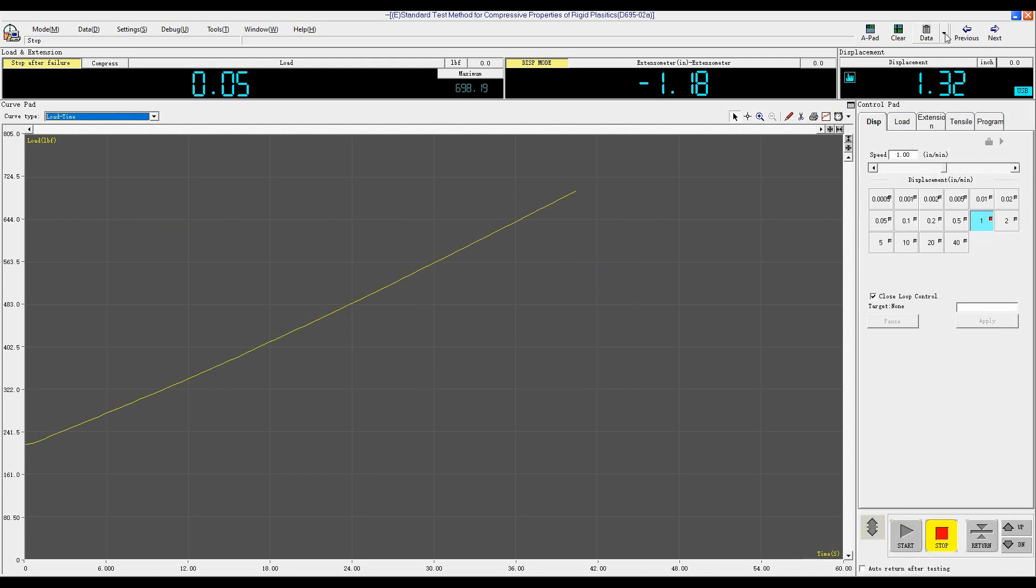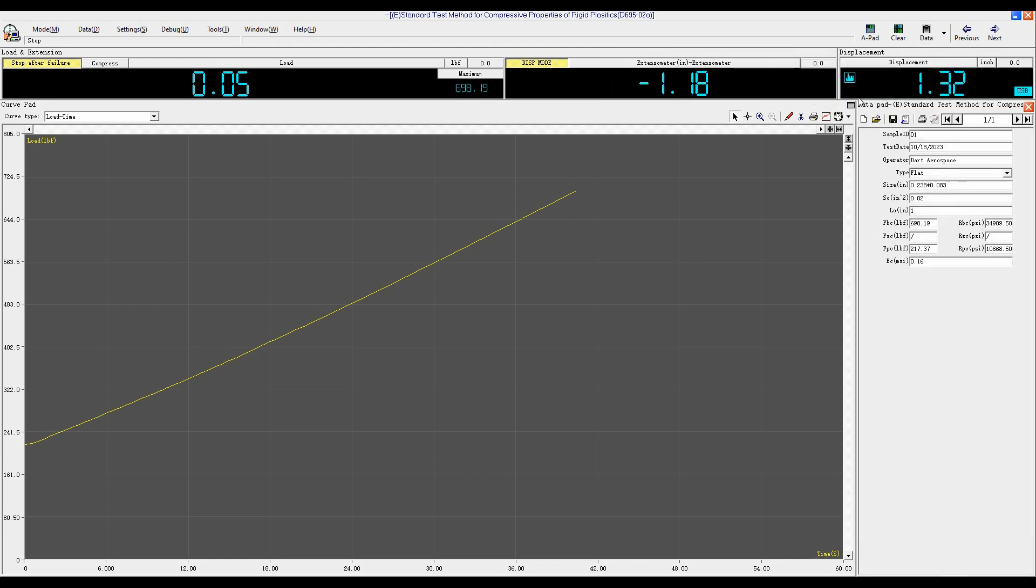Now we will perform a compression test. First choose the testing standard, like Compress Test of Plastic ASTM D695, and then click New to input the sample information.